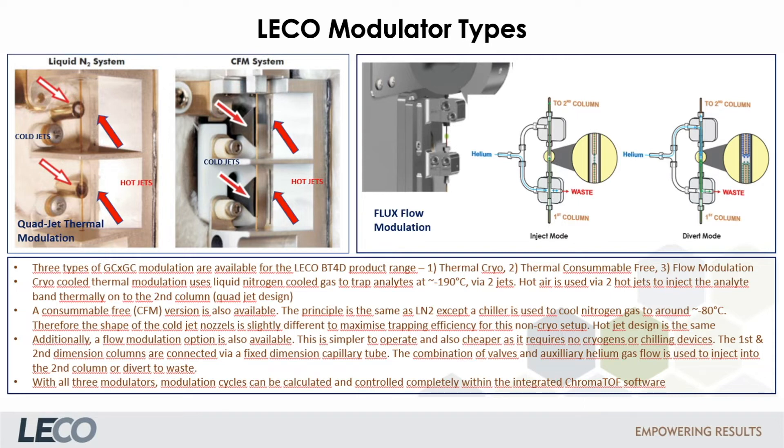Cryo-cooled thermal modulation uses liquid nitrogen-cooled gas to trap the analytes via two jets. Hot air is used via two jets to inject the analyte band into the second column — this is also called the quad-jet design. A consumable-free version is also available using a chiller to cool the nitrogen gas; the cold jet nozzles are shaped slightly differently to maximize trapping efficiency, while the hot jet design remains the same. Additionally, a flow modulation option is available. This is simpler to operate and also cheaper, as it requires no cryogenics or chilling devices, though its performance characteristics are not as good compared to thermal modulation. All three modulators can be controlled completely via the chromatography software.